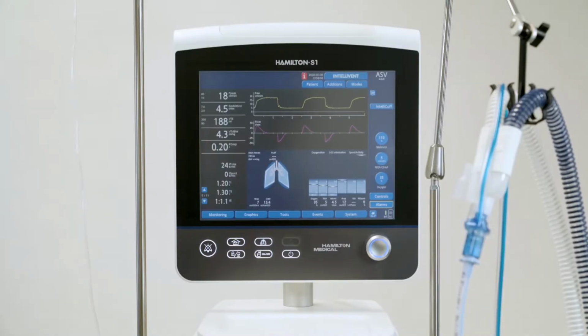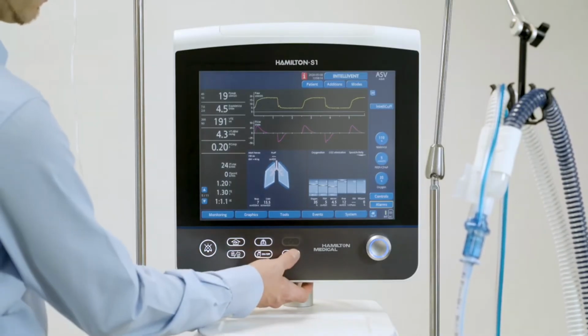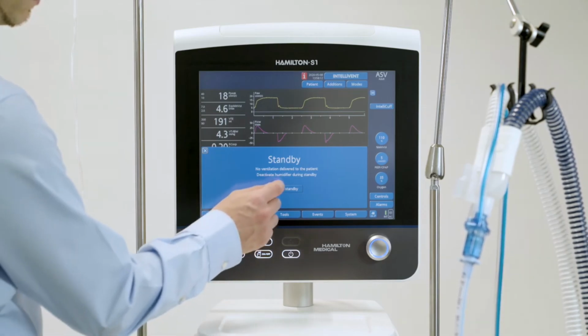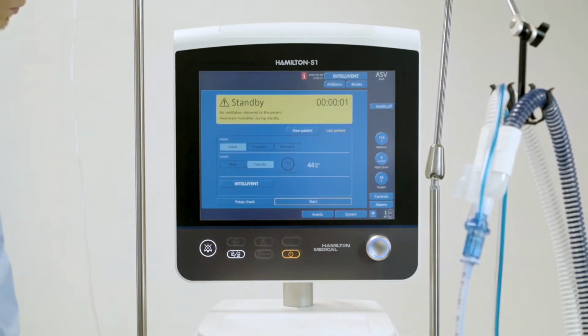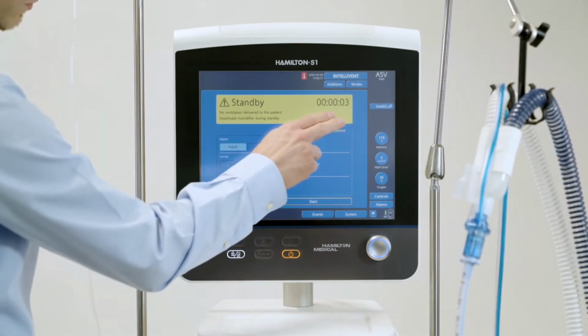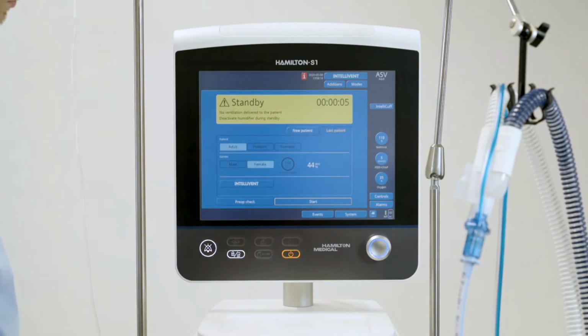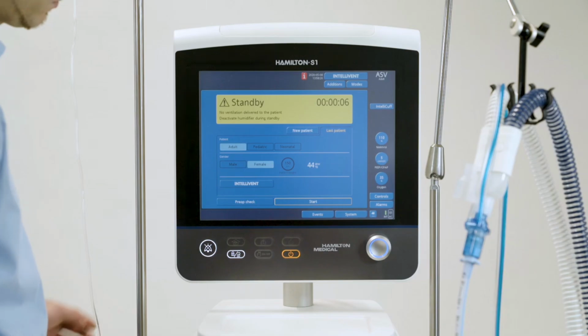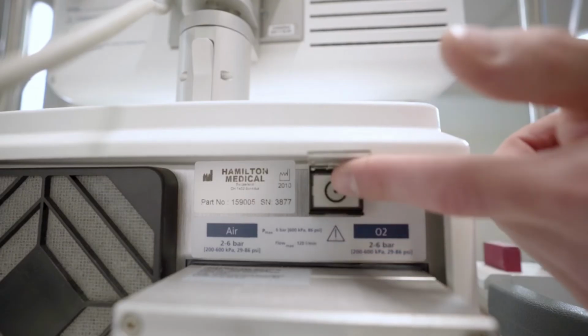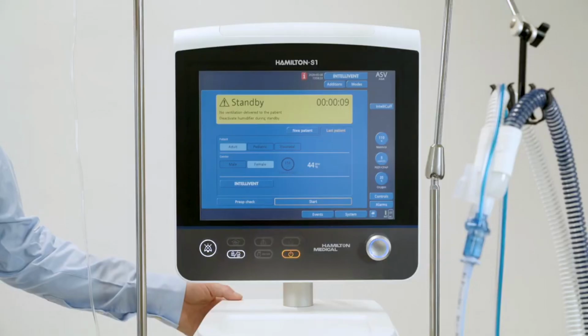To stop ventilation, press the Standby key. Then, touch Activate Standby. The device enters standby, and the yellow counter shows the time elapsed in this mode. Note that while using IntelliCuff, you must first deflate the cuff and turn off IntelliCuff before turning off the ventilator. To turn off the ventilator, press the power button on the back of the ventilator.